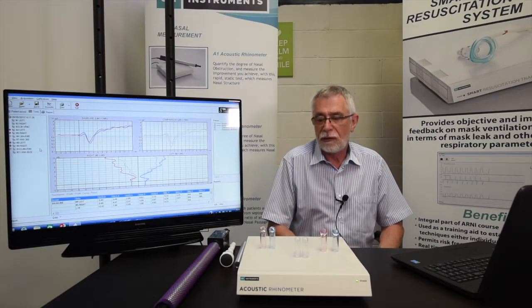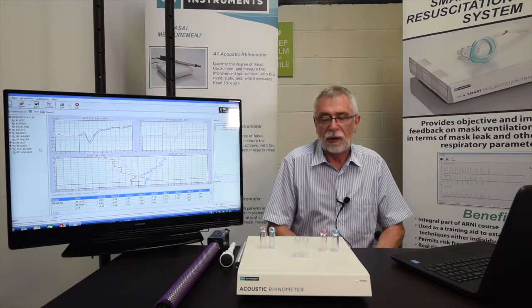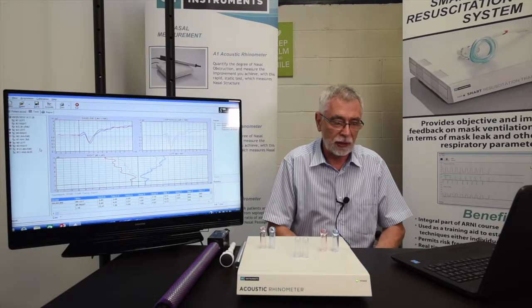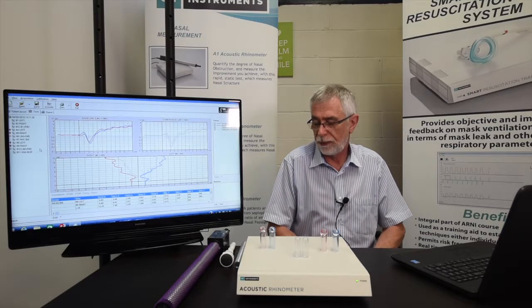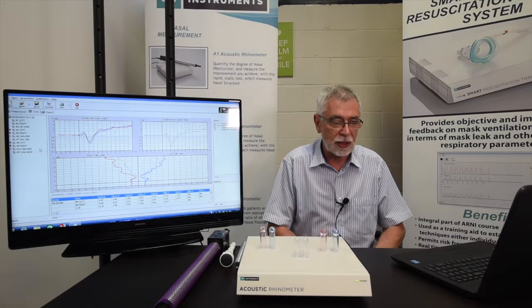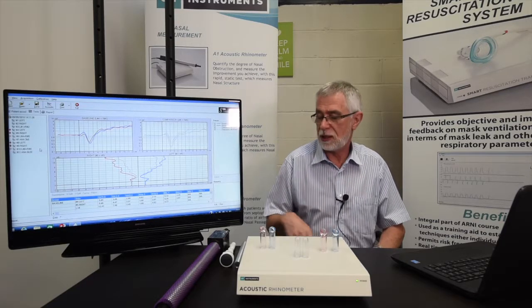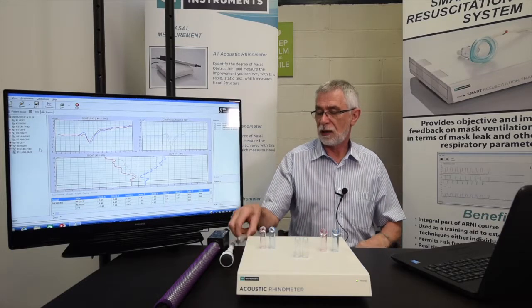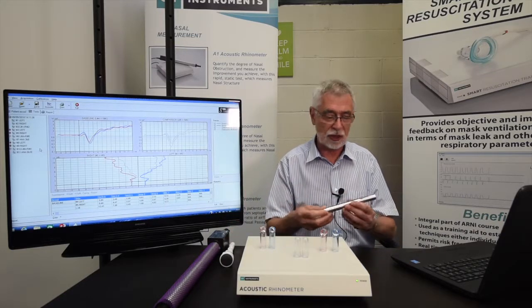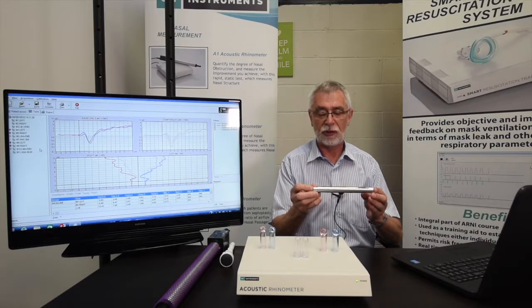We have two versions of the A1 system, a clinical and a clinical research. The clinical one is basically what I've shown you there. The clinical research adds some additional software as well as additional hardware for setting up and checking the system.